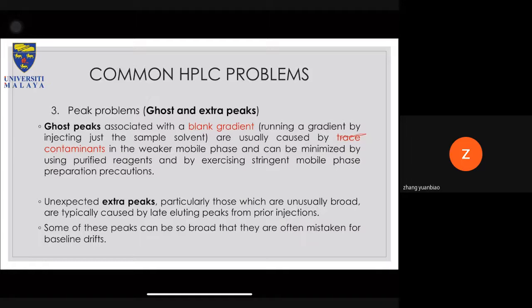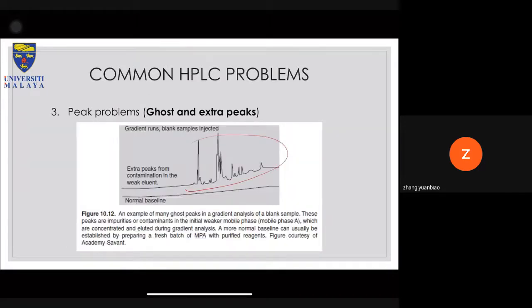Unexpected extra peaks, particularly those which are unusually broad, are typically caused by a late eluting peak from a prior injection. Okay, so this can also be the cause of a ghost peak. Some of these peaks can be so broad that they are often mistaken for baseline drift. So what do I mean by that? It's like here. This one is a ghost peak, whereby you can see it's a blank run, but you see peaks coming out. Okay, that is what it means by ghost peaks.